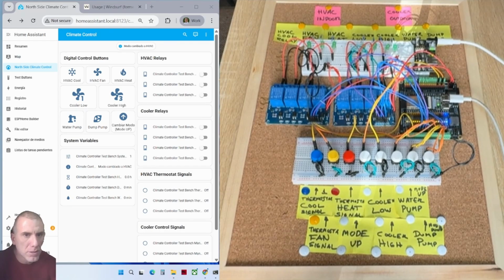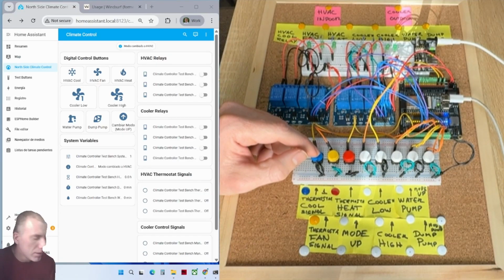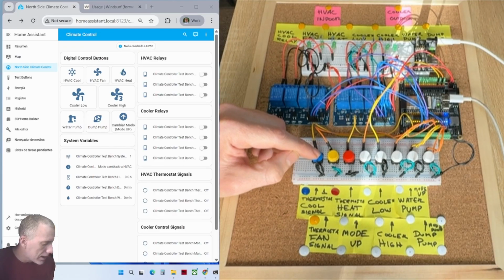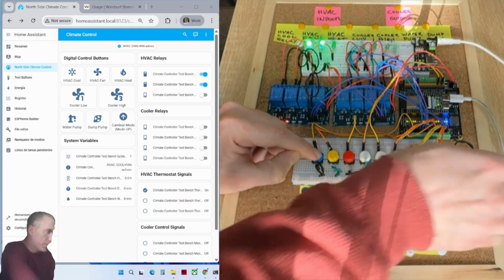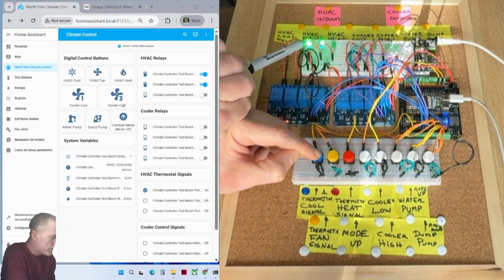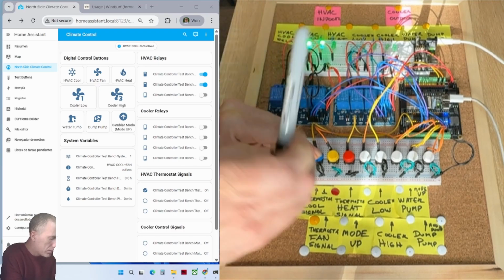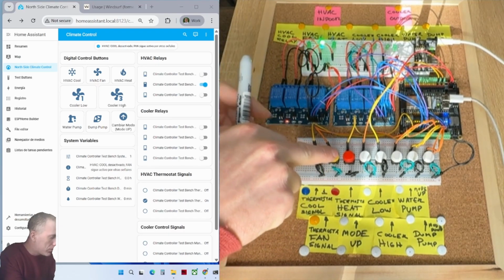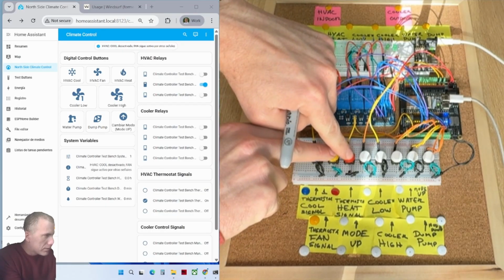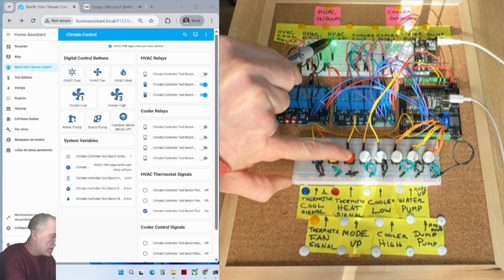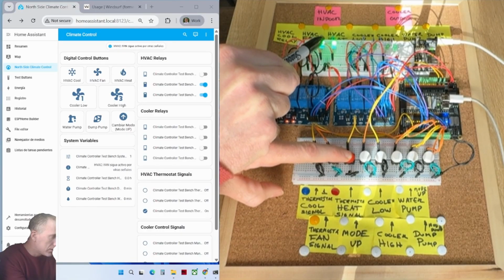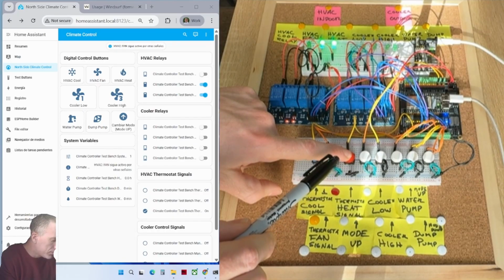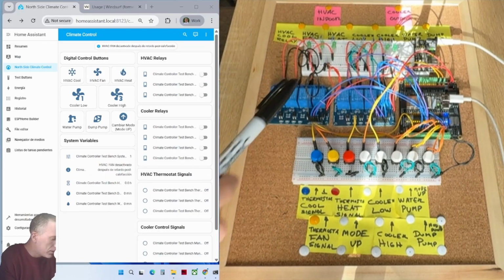Note that for this mode of operation, HVAC, we have the same functionality with the physical buttons that simulate each signal when I have the button pressed. For example, this signal is cool, and we have cooling and fan active. If I press only the fan signal, now we have fan only, and if we press heat, we have fan and heat process. Activated. If I release the button, we have the delay of the activation of the fan.